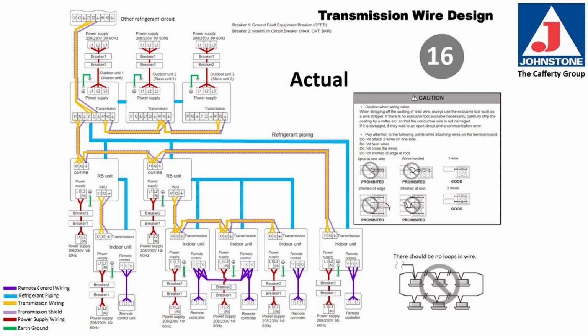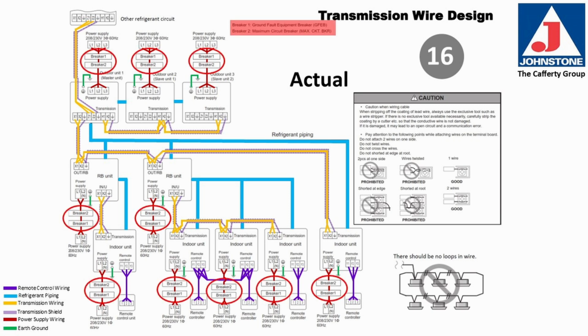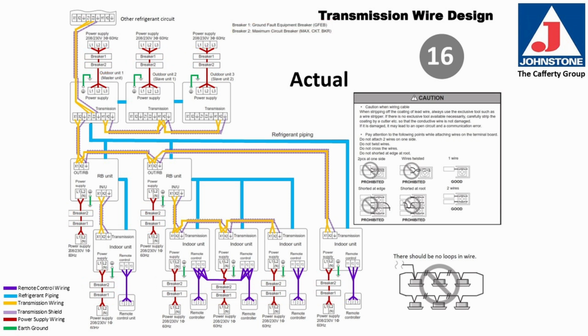Please carefully follow the wiring diagram in your installation instructions. You'll notice that the power lines on each of the indoor units are showing two breakers. Breaker 1 is a ground fault equipment breaker, or GFEB. Breaker 2 is your maximum circuit breaker. If you have multiple refrigerant circuits on this job site, these are the connections for the wiring between this refrigerant circuit that we're looking at and the other refrigerant circuit that's on site.